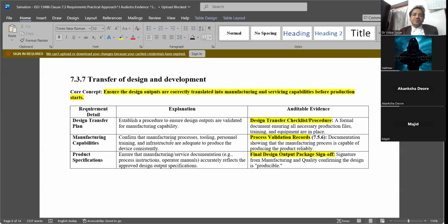See guys, you need to give a lot of documentation. From your raw material, R&D has to give: this is the raw material, who is the supplier, this is the raw material specification, these are the tests we have done. But of course, the main important things are the final technical specification of the product and the product process parameters. They need to give the SOPs. SOPs are basically given by R&D, it's not done by production. What are the parameters, how you measure, measuring functions or monitoring systems? Total data of the validation, what they have done, total data of verification, from inputs to verification, everything, technical specifications. What are the inline or in-process QC?